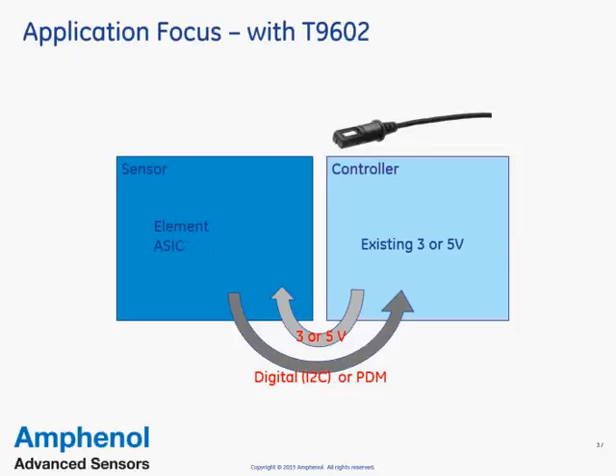With the 9602, we do away with a number of those components. The sensor itself has a built-in ASIC, and its power supply is either 3 or 5 volt, which is normally found on any controller with microprocessing on board. The output is either digital I2C or a pulse density modulated signal. So the T9602 concept saves components by allowing the sensor chip to communicate directly with the controller, bypassing the need for converters and power supplies, using the 3.3 or 5 volt rail to power the sensor.